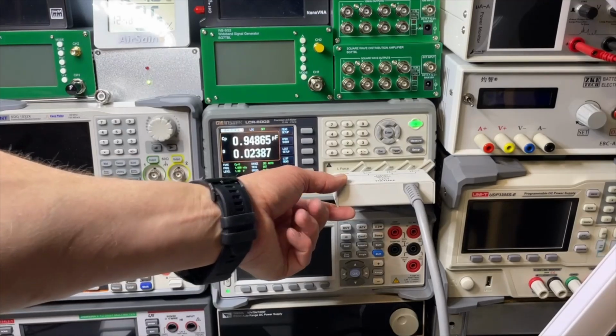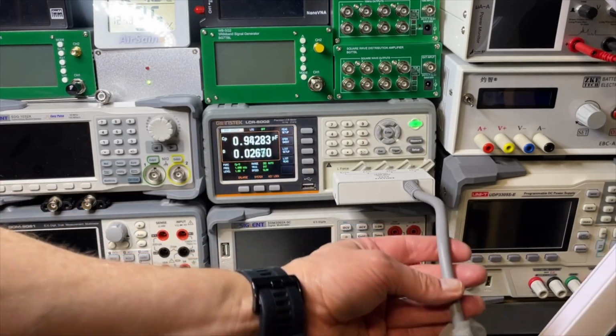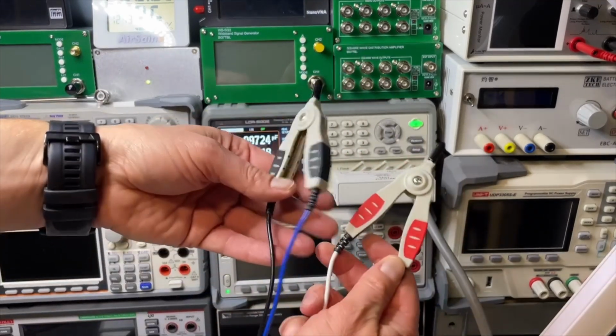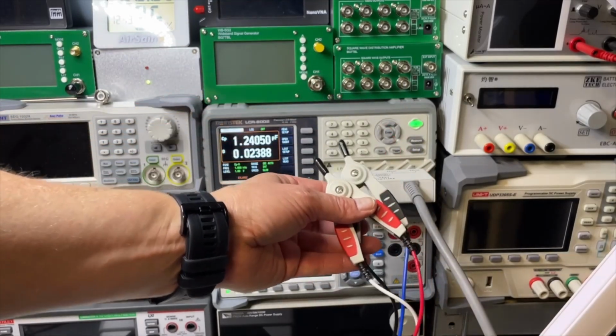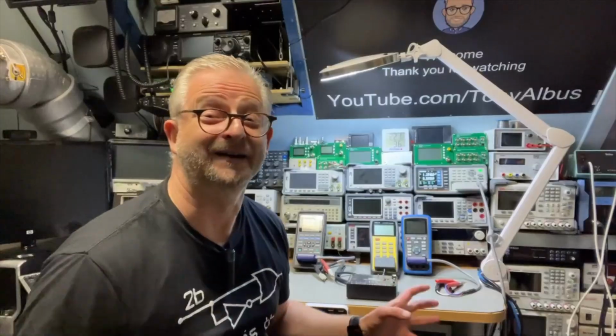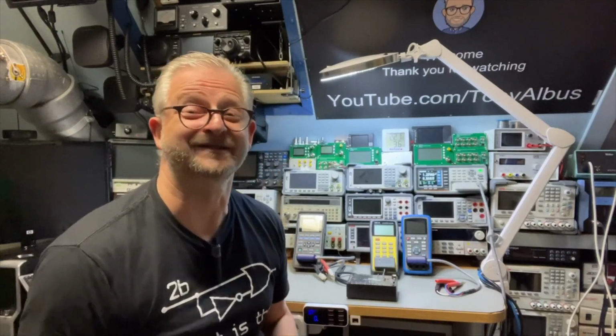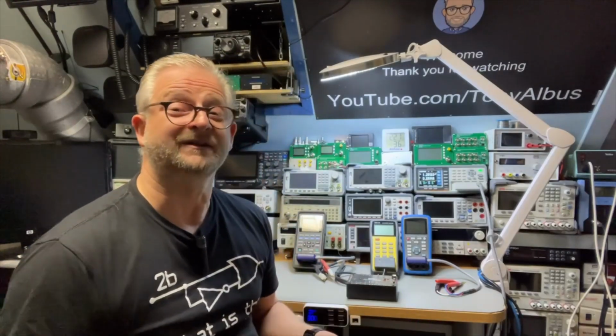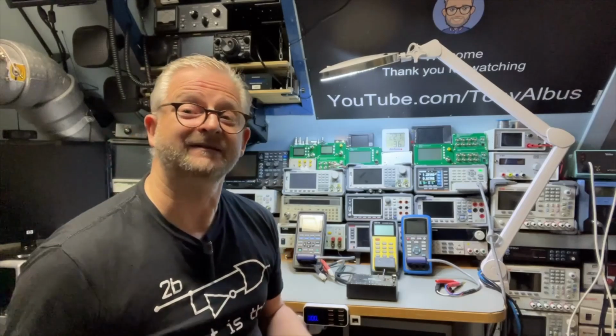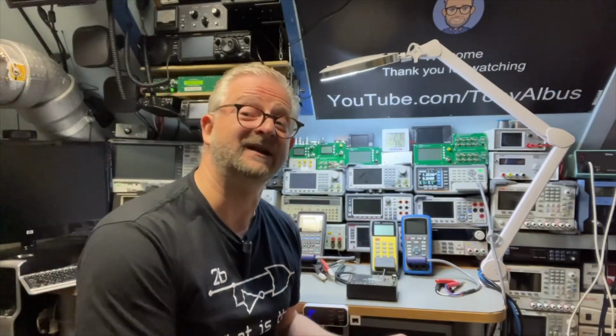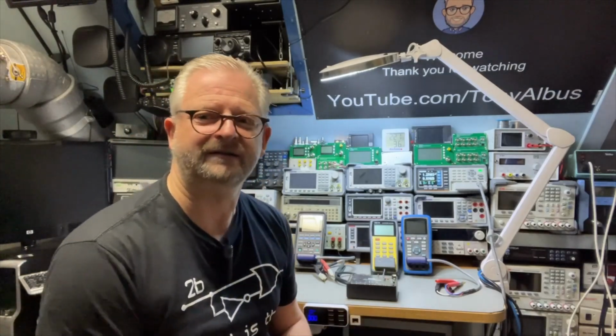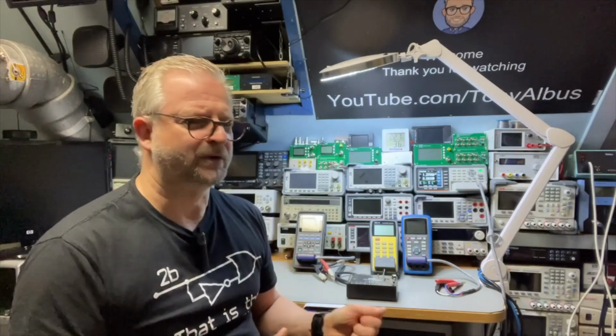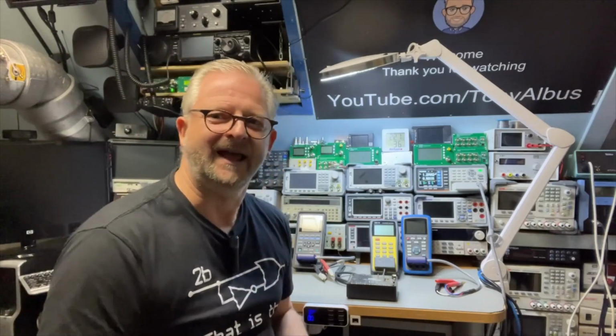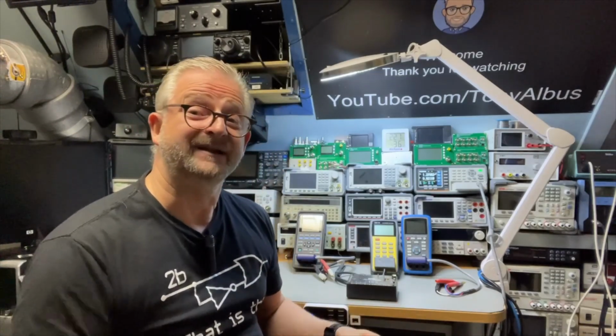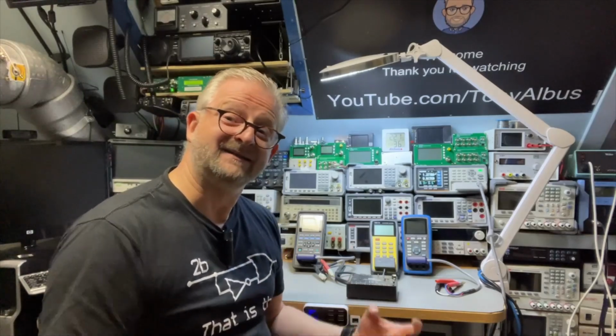I'm using here a real fixture. All shielded cables here and with higher quality Kelvins, so we should get very good results here. Knowing that I'm not a very advanced user of the LCR meter, I want to start in auto mode, and my experience with the LCR tweezers that I did videos on, it's best to start just on 1 kHz, 0.5, 0.6 volts, and then we can later see if we adjust the frequency, if we can get a better result or not.